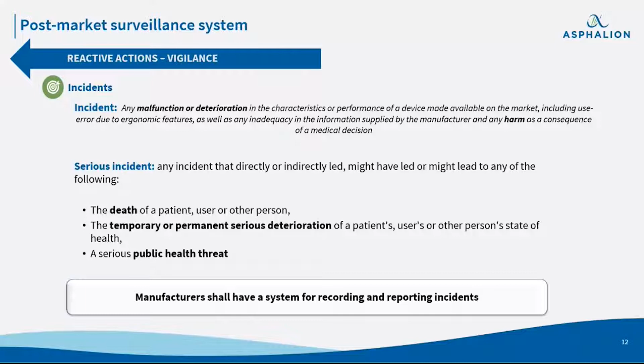Period of reporting. Well, as a general rule, the period of reporting should take into account the severity of the serious incident. Manufacturers should report any serious incident immediately after they have established a causal relationship between the incident and their device, or when the causal relationship is reasonably possible, and not later than 15 days after they become aware of the incident. In the event of death or unanticipated serious deterioration in a person's state of health, the report should be provided immediately after the manufacturer has established or as soon as it suspects a causal relationship, but no later than 10 days after the date on which the manufacturer becomes aware of the serious incident. In the event of a serious public health threat, the report should be provided immediately and no later than 2 days after the manufacturers become aware of the threat.